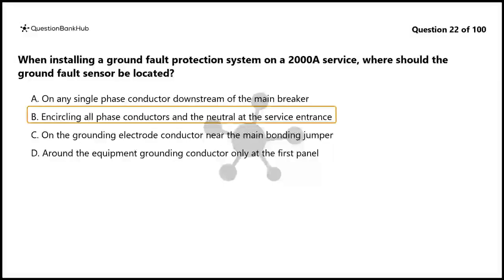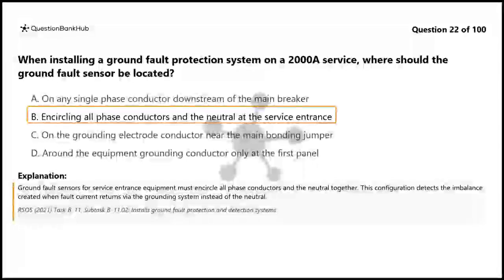The correct answer is B. Encircling all phase conductors and the neutral at the service entrance. Ground fault sensors for service entrance equipment must encircle all phase conductors and the neutral together. This configuration detects the imbalance created when fault current returns via the grounding system instead of the neutral.